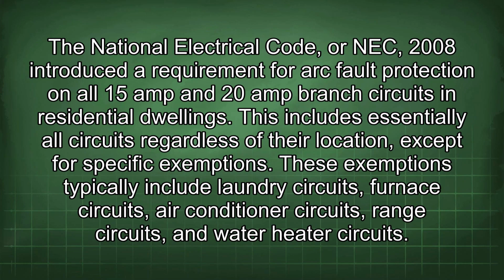The National Electrical Code, or NEC, 2008 introduced a requirement for arc fault protection on all 15 amp and 20 amp branch circuits in residential dwellings. This includes essentially all circuits regardless of their location except for specific exemptions. These exemptions typically include laundry circuits, furnace circuits, air conditioner circuits, range circuits, and water heater circuits.